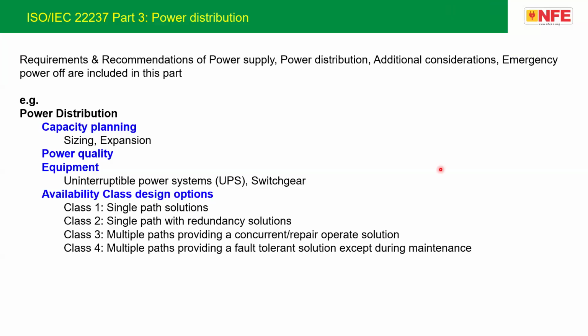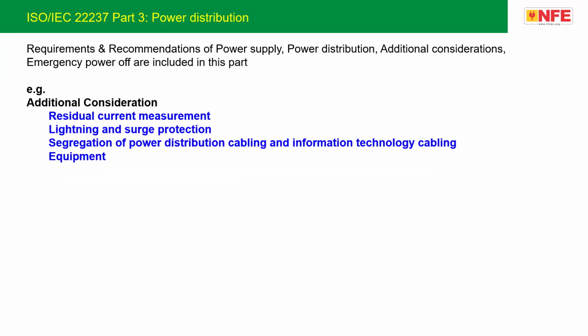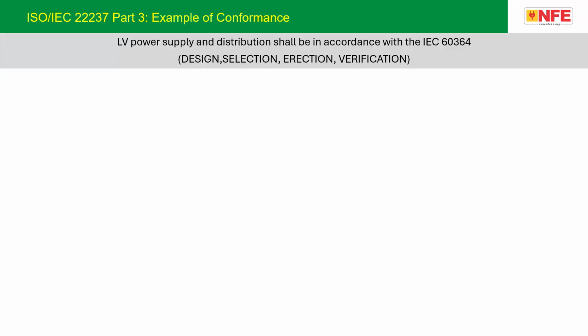Actually, this 22237 is the base for TIA or probably the Uptime Institute. Basically, ISO is mandatory for every WTO nation. Also, the sustainability goals are set by the UN and followed through this mechanism of ISO and IEC. If we look at part 3, it also talks about additional requirements. For example, these are the three additional requirements, other than power supply and power distribution: the residual current measurement, lightning and surge protection, and segregation of power distribution cabling from information technology cabling and equipment. So these are the requirements.